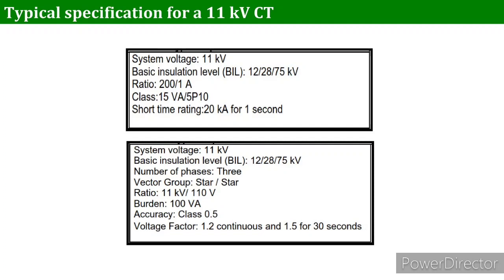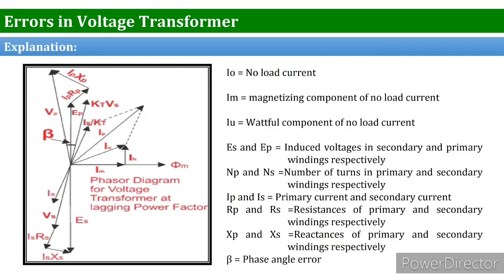Some typical specifications mentioned on the nameplate of a PT include: system voltage, BIL (basic insulation level) at three levels — 12, 28, and 75 — ratio, and accuracy class as discussed in the previous lecture. Additionally, burden ratings, accuracy class, voltage vectors, vector groups, and number of phases are all mentioned on the nameplate or data sheet. Before installing, you can refer to these parameters for reasonable selection of your potential transformer.